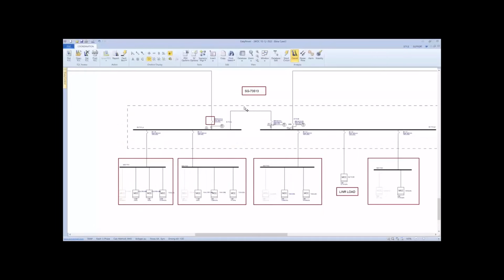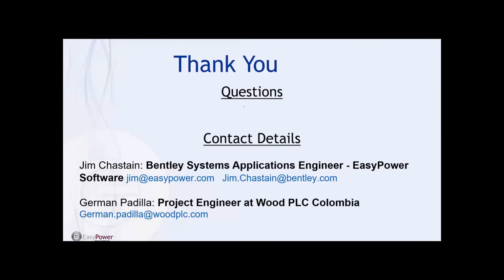So the incident energy was artificially low because of the 2-second max. Now if you go back and change your 200 seconds down to 2 seconds, you'll get a more realistic result, because only the low voltage issues will be limited to the max time. Does that make sense? Alexander, did that make sense? Yeah.